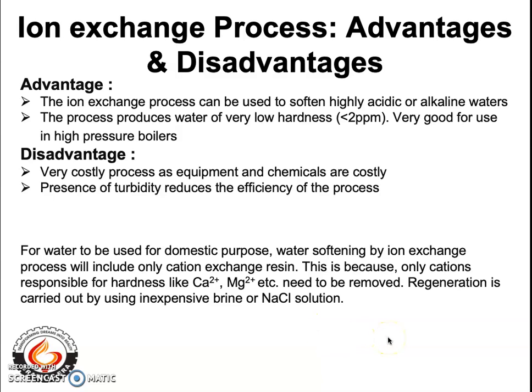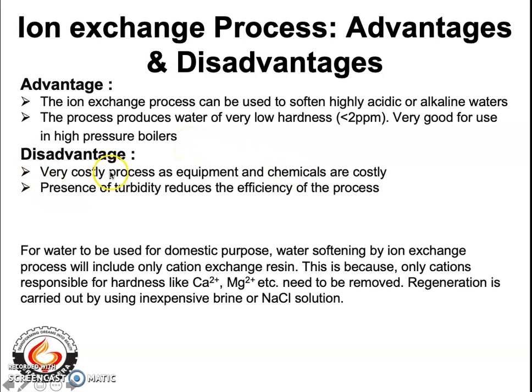Now let us look at the advantages and disadvantages of the ion exchange process. The advantages are: the process can be used to soften highly acidic or alkaline water; it removes hardness to a level of less than 2 ppm, giving absolutely soft water; and it is very suitable for use in high pressure boilers. The disadvantage is that the process is very costly, as the equipment and chemicals used are always expensive.